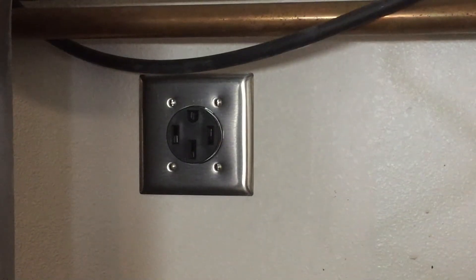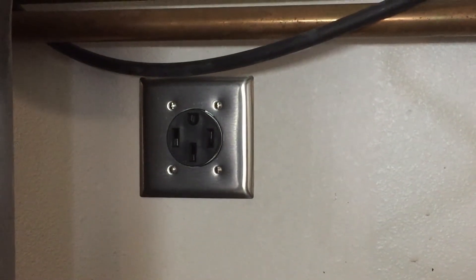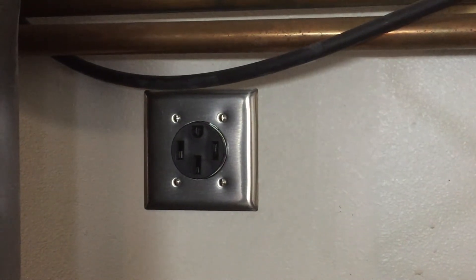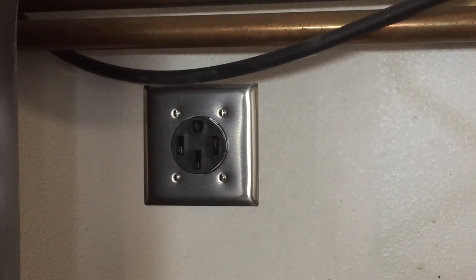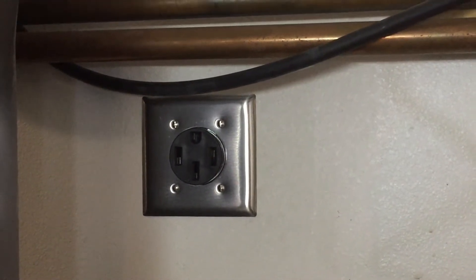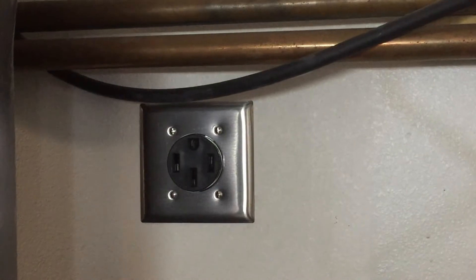Let's get into the garage. So this is what they installed in the garage — it was a NEMA outlet, that's for the 40A, and they installed a 50A breaker and using the 50A cable.